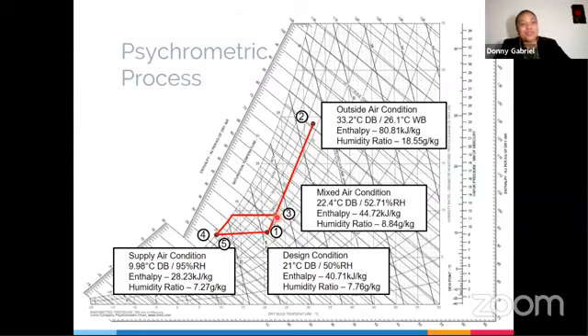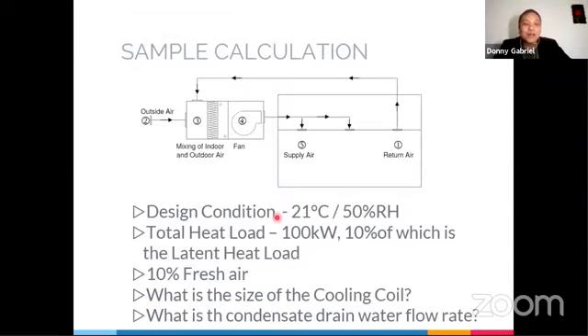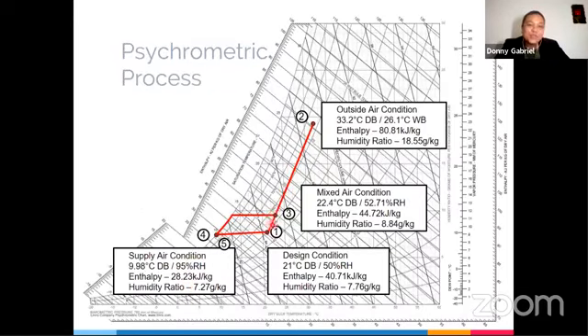Because this is a graphical representation, the psychrometric process is a graphical representation, you can calculate it also graphically. Our condition requires us 10% of fresh air. So this is 10% fresh air. This line is 10% of this longer line. Okay? Clear? So, when outdoor air and return air mix together, this is the resulting condition, point 3. So outdoor air and design condition mixed together, the resulting condition is at point 3.